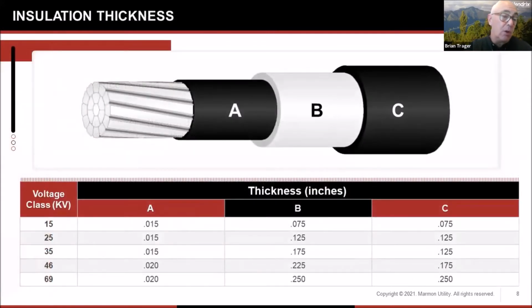And of course, due to Ohm's law, as I increase my voltage, I want to limit the charging current on the outside of the jacket. So I need more insulation. So at 15 kV, I've got 75 mils plus 75 mils for the 2 layers, which gives me about 3.8 millimeters of total wall thickness. Whereas when I'm up at 69 kV, I have 250 mils plus 250 mils for the 2 layers, 500 mils, half an inch, about 12.5 millimeters. So that's a lot thicker, if you will.